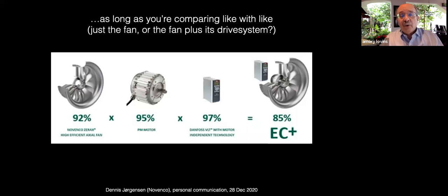Next generation inverters will progress from yesterday's silicon and today's silicon carbide switches to tomorrow's, just coming on the market, gallium nitride or GaN, G-A-N switches, which are so efficient that the inverter typically needs no cooling. Oh, and by the way, axial fan motors and sometimes their inverters are often sited in the airstream you're moving, often supplying cooled air to cool a building. So downstream efficiency not only saves drive power, but can also avoid rewarming the air that you just cooled.